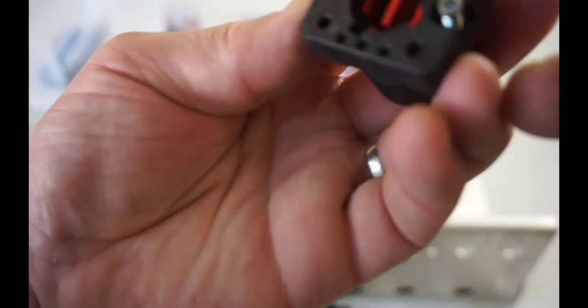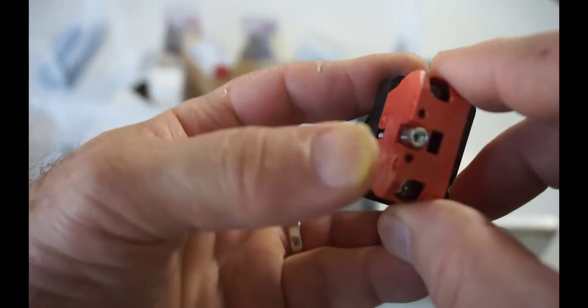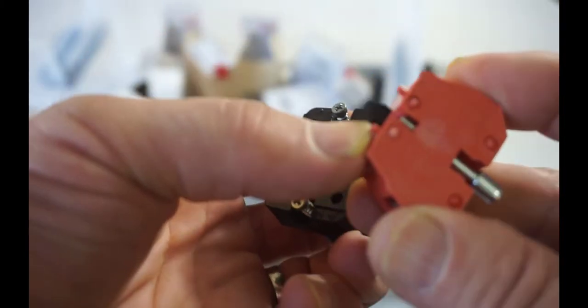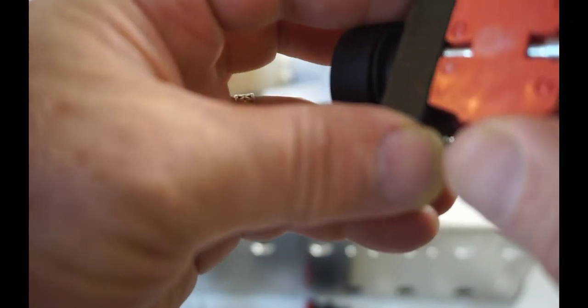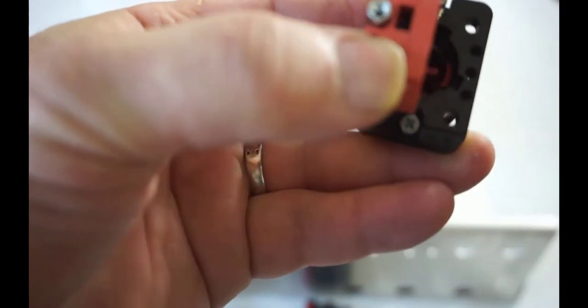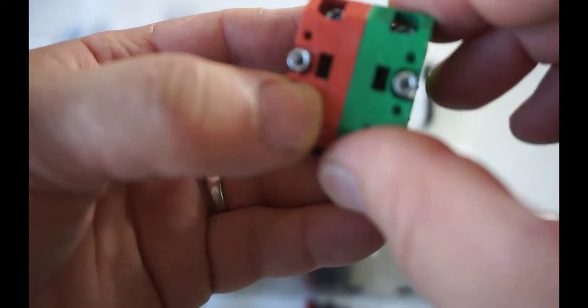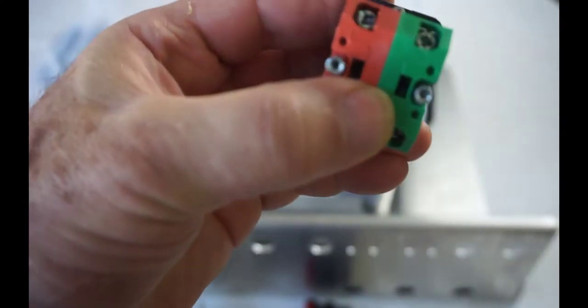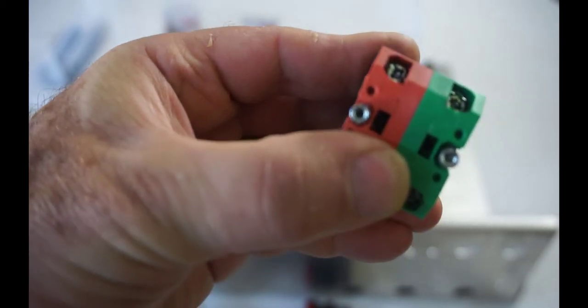You're able to put these on here and they drop in place very gently. There's a couple little tabs, little pins on here. See those pins there? Those line up with the holes. You drop them in place gently and tighten this down. If you want a set of normally open and normally closed contacts, you put one on either side. That gets you a set of normally open and normally closed off the same push button.